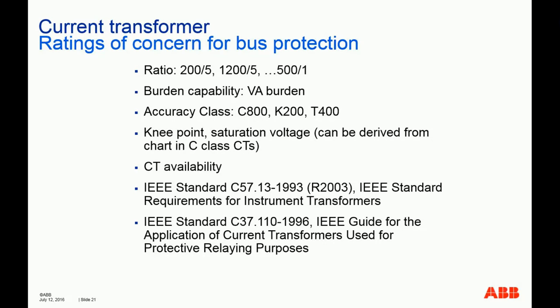So ratings for current transformers, as we all know, there are different ratios for the current transformers. Okay, and then there are different accuracy classes. So what do they mean? The accuracy definition basically says that for relay CTs, ANSI and IEEE define the limit of 10% for the ratio error. So it allows 10% error for a steady state symmetrical current. What does symmetrical mean? There's no DC offset. So it allows 10% ratio error for 20 times secondary current at a standard rated burden.